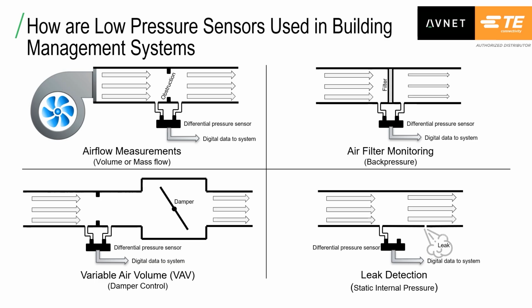The last major application is for leak detection in air moving systems. Here, the sensor is monitoring the overall system pressure, and a drop in that pressure can indicate either a leak somewhere in the system or trouble with fans or blowers used to move the air, or the dampers or controls used to regulate the airflow.